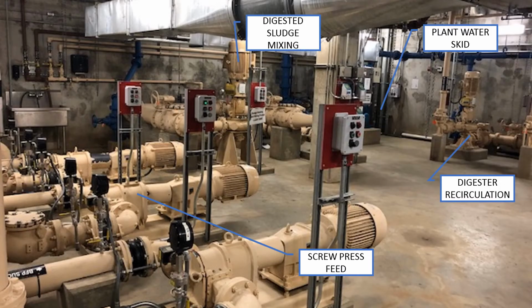Down in the basement of the digester equipment building is where all the mechanical equipment is housed. There are some digester mix pumps for each of the digesters. There are recirculation pumps that are taking material from the digesters and continuously pumping it up and through the heat exchangers. There are a couple of pumps dedicated to the digested sludge storage tank to keep that material mixed, and then a series of pumps that are taking the digested sludge and pumping it up to our screw presses. There are some automated valves down in this basement as well as a plant water system.